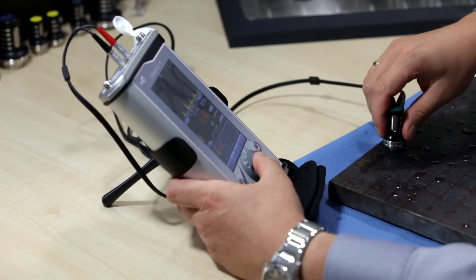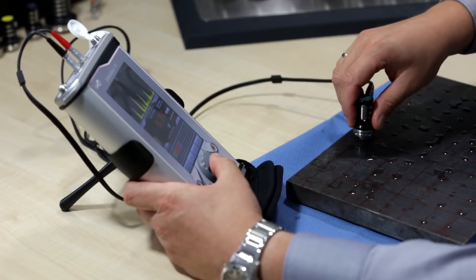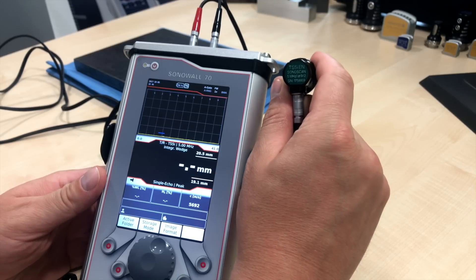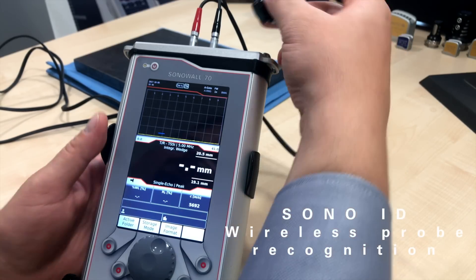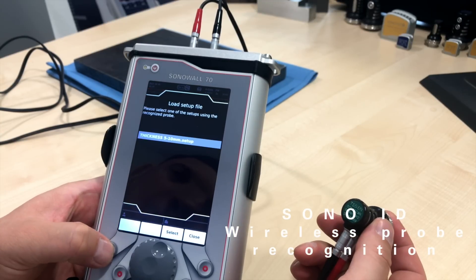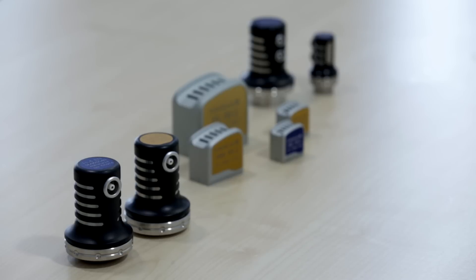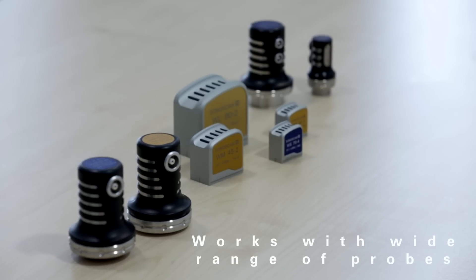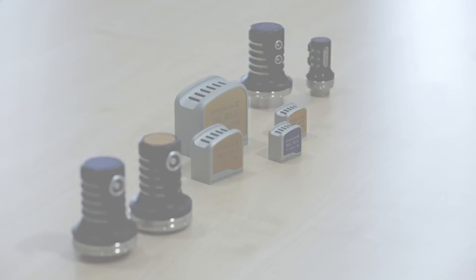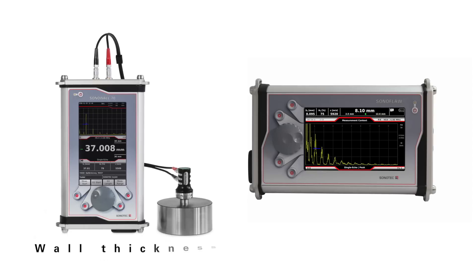Many intuitive functions are implemented to significantly reduce operating time so you can focus on the actual application task. The device is equipped with innovative Sono ID wireless probe recognition, which allows you to quickly load the setup for the probe you would like to use. A wide selection of Sonotec probes, and the fact that other manufacturers' probes can be connected easily, makes the Sono Wall 70 the most versatile wall thickness device on the market. It can be used in two operating modes: wall thickness and flaw detector mode.